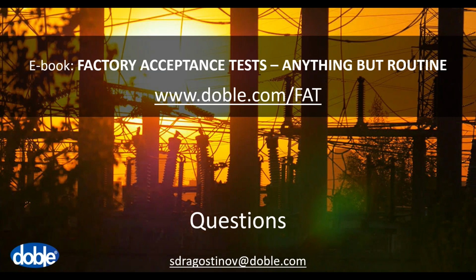Yeah, it depends what the purpose of the testing actually is. Is it a fault? Are you looking to check for a fault, or is this just a regular condition assessment or commissioning of the unit? So if it's just a regular condition assessment, I would recommend transformer ratio, winding resistance, and important for the insulation system, this is capacitance and tan delta measurement. Also magnetizing current to check for possible short circuit and problems related with the core.